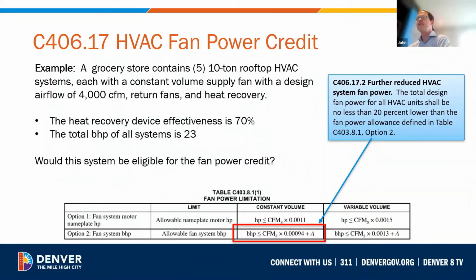Another example here is a grocery store that contains 10-ton rooftop HVAC systems, each with a constant volume supply fan, 4,000 CFM return fans, and heat recovery. This is a new credit for Denver, by the way, the fan power allowance, reduced fan power. If the heat recovery device's effectiveness is 70% and the total brake horsepower, BHP, of all systems together is 23, would this system be available for credit?